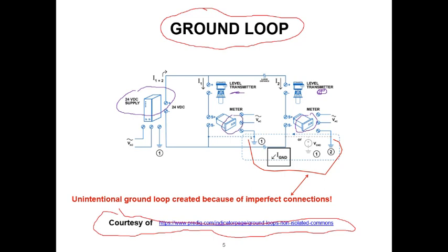Okay, so notice right here, the power supply for the meter is tied to ground, and the power supply for the meter is tied to ground. But those two grounds physically are separated. I don't know how far they're separated, but they're separated. They're not to the same point.